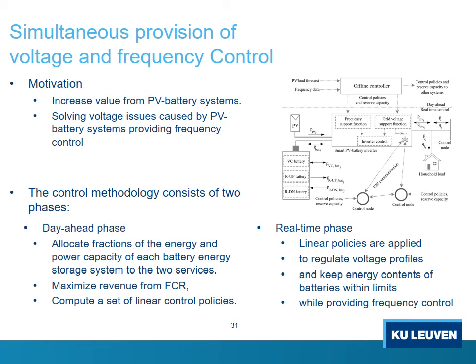Why do we have a dedicated virtual battery for upward frequency regulation and another one for downward frequency regulation? Because in distribution networks with high photovoltaic penetration, you sometimes cannot respond to upward frequency regulation. For instance, during midday, when there's a voltage rise, you cannot discharge the batteries, since that would make the voltage rise problem even worse. But you can respond to downward frequency regulation, because this helps mitigate the voltage rise problem.